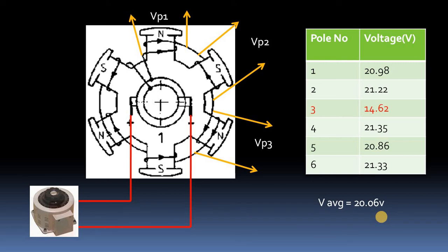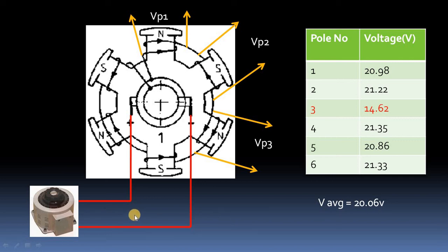From these readings, we can see that pole number three has a voltage which is less than the average voltage, so pole number three has shorted turns. The process is simple: apply voltage using the variac, measure voltage across all poles, and whichever pole has a voltage less than the average voltage has shorted turns.